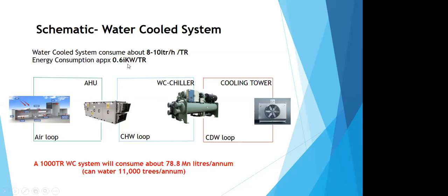But I have taken a general consumption of chiller, which is around 0.6 IKW per ton. Now, for a typical 1,000-ton water-cooled system, which is operating almost 8,000 hours per annum, will consume roughly 78 to 80 million liters of water per annum. That is huge. And one can water almost 11,000 trees in a year by the amount of water being consumed.